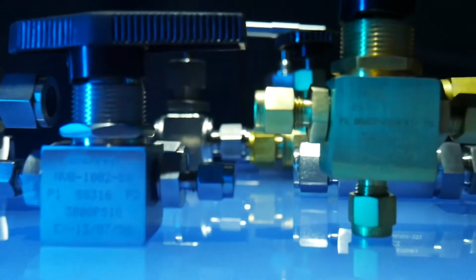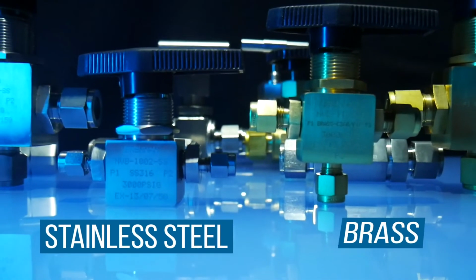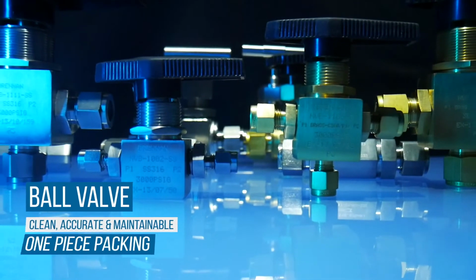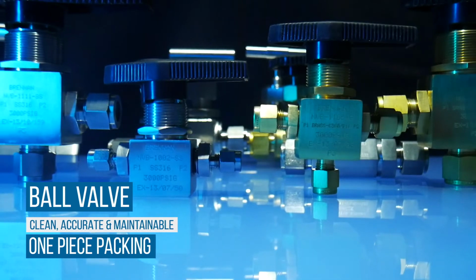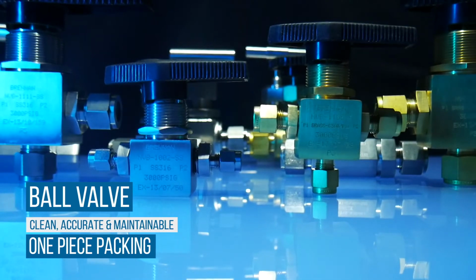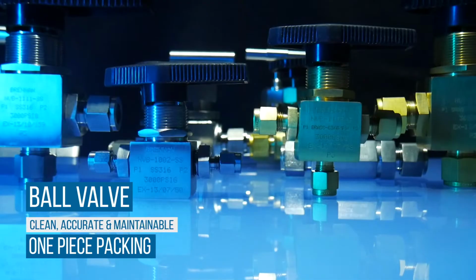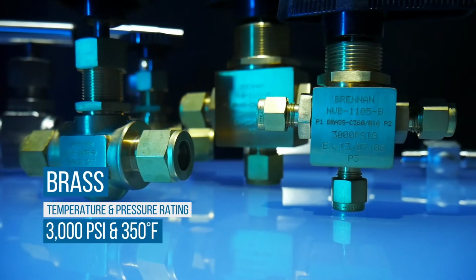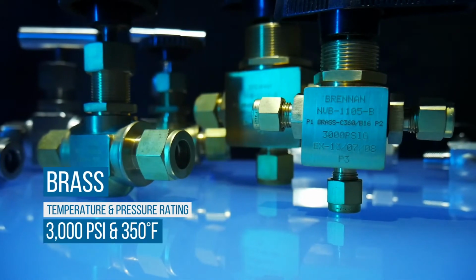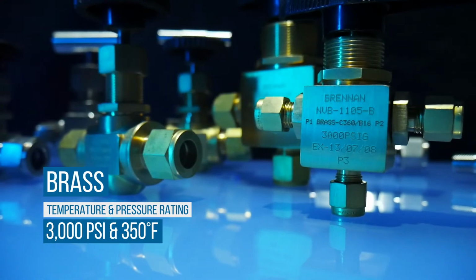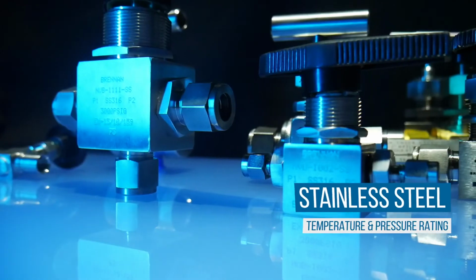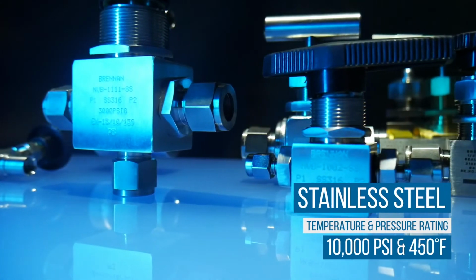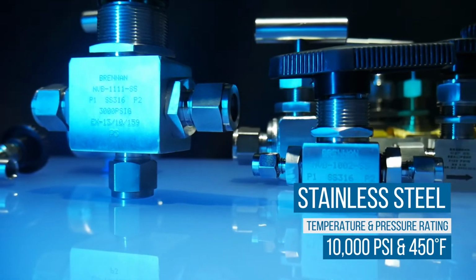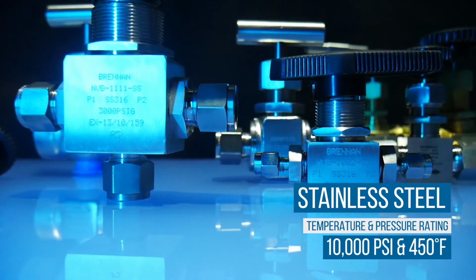Popular ball valve designs are available in stainless steel and brass and incorporate one-piece packing for clean and accurate samples, as well as designs that allow for a drop-in fit for easy replacement of the packing. Brass instrumentation ball valves are rated for pressure up to 3,000 psi and temperatures to 350 degrees Fahrenheit, while stainless steel instrumentation ball valves are rated for pressures up to 10,000 psi and 450 degrees Fahrenheit.